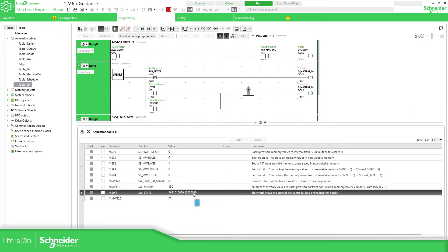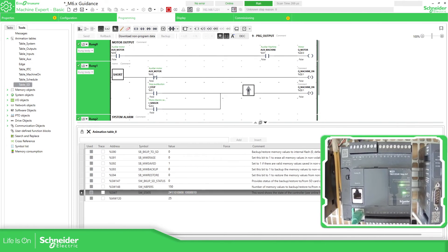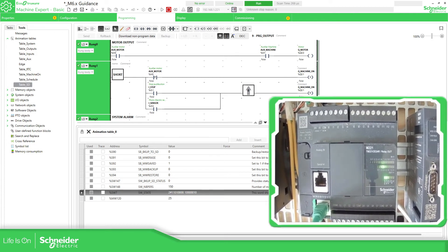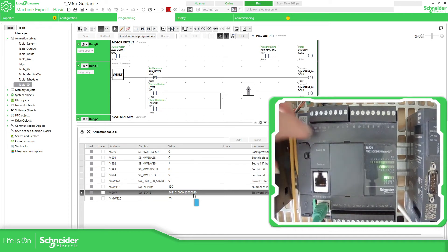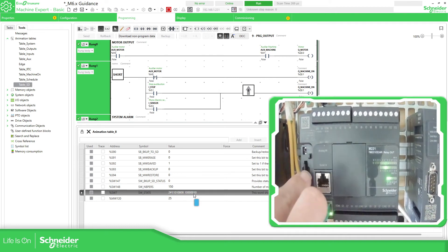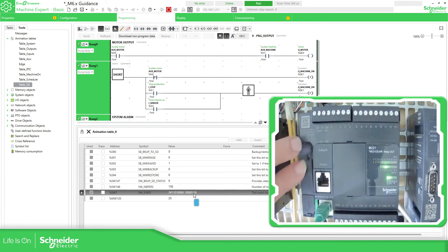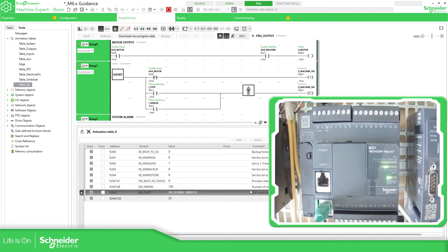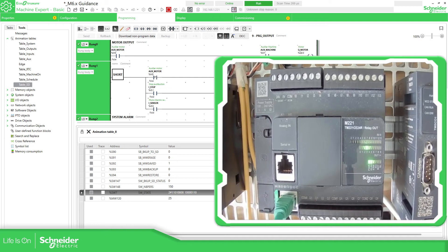As I mentioned, bit 2 of %SW7 indicates the presence of the SD card. What I'm going to do now is insert the SD card and bit 2 of this word should change. Now I'm putting the SD card in. You can see there has been a change — bit 0, 1, and 2, which is the third bit. The status of the SD card LED is now off, indicating no access — we are not doing anything with it yet.